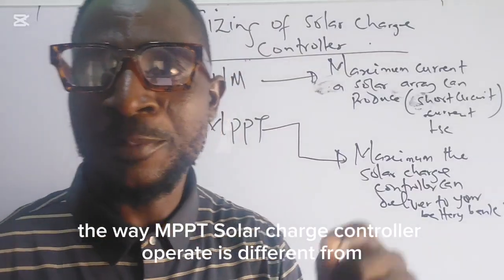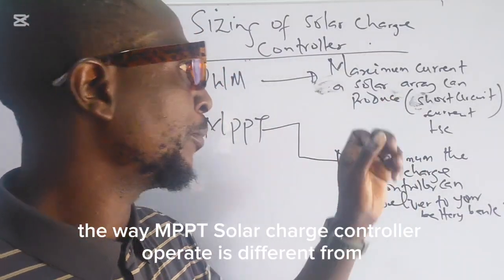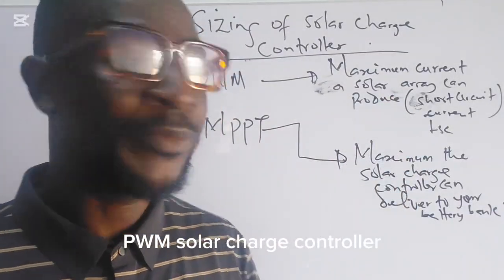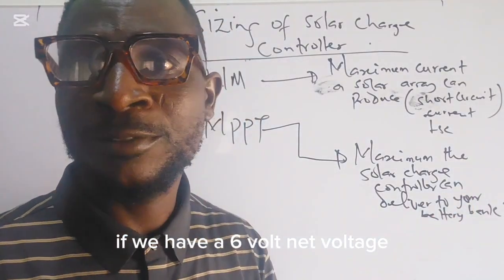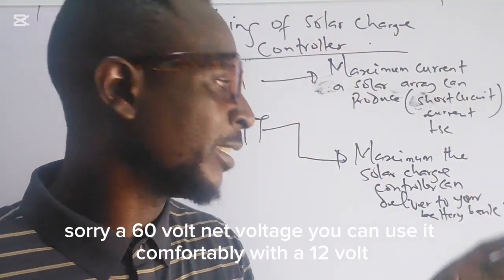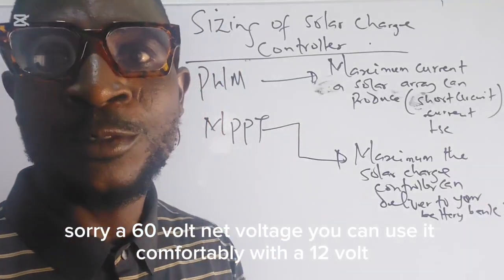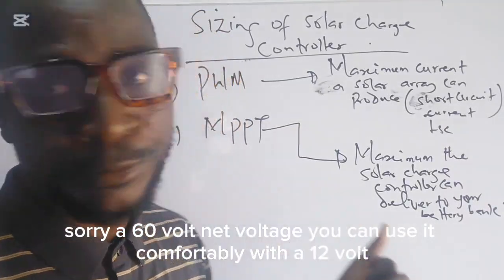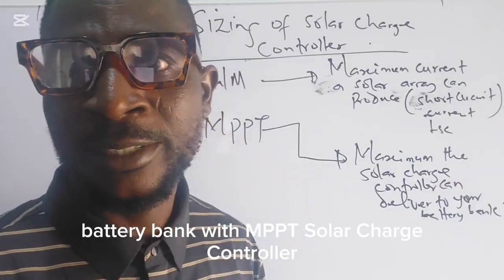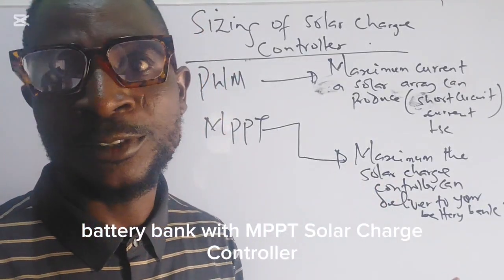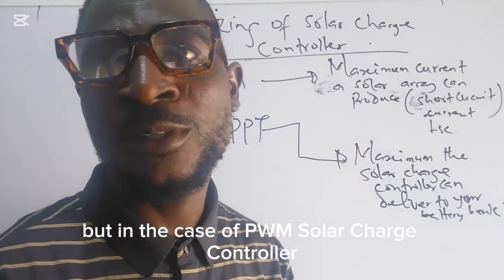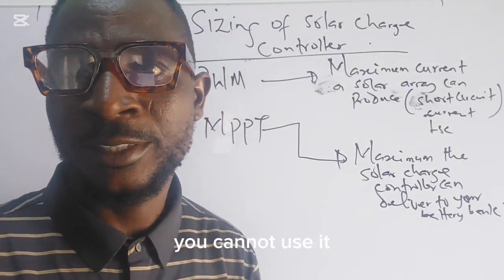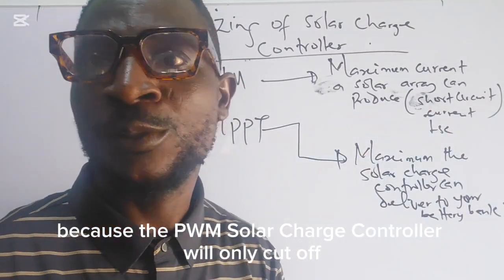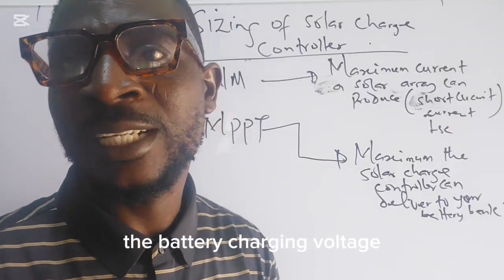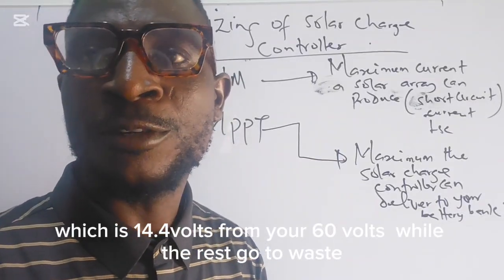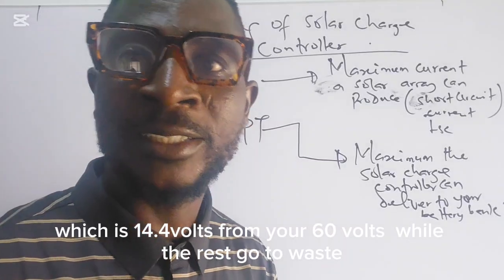And the way an MPPT solar charge controller operates is different from a PWM solar charge controller. If we have a 60-volt array voltage, you can use it comfortably with a 12-volt battery bank with an MPPT solar charge controller. But in the case of a PWM solar charge controller, you cannot use it, because the PWM solar charge controller will only take the battery charging voltage, which is 14.4, from your 60 volts, and the rest goes to waste.